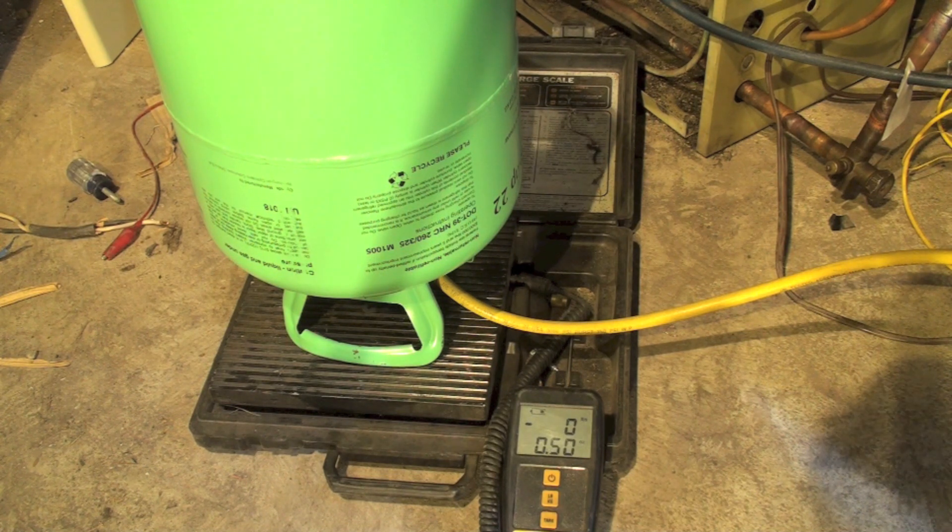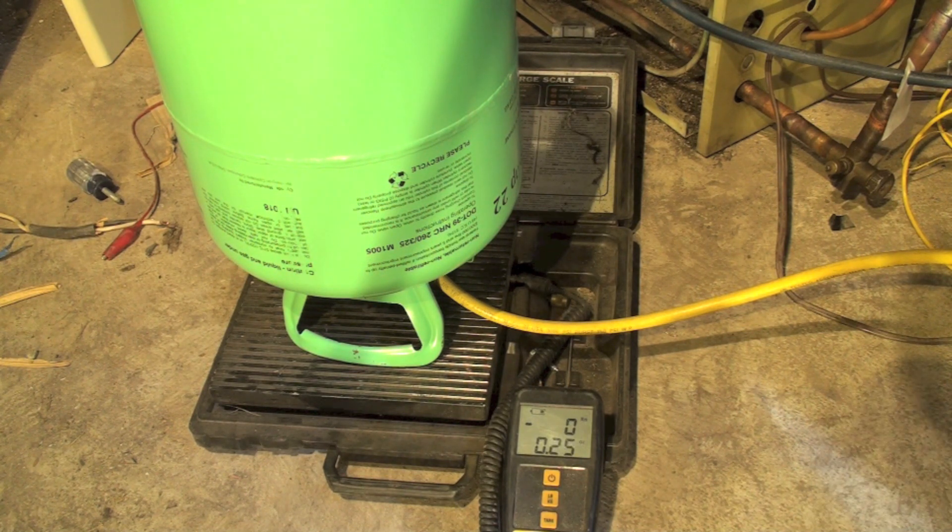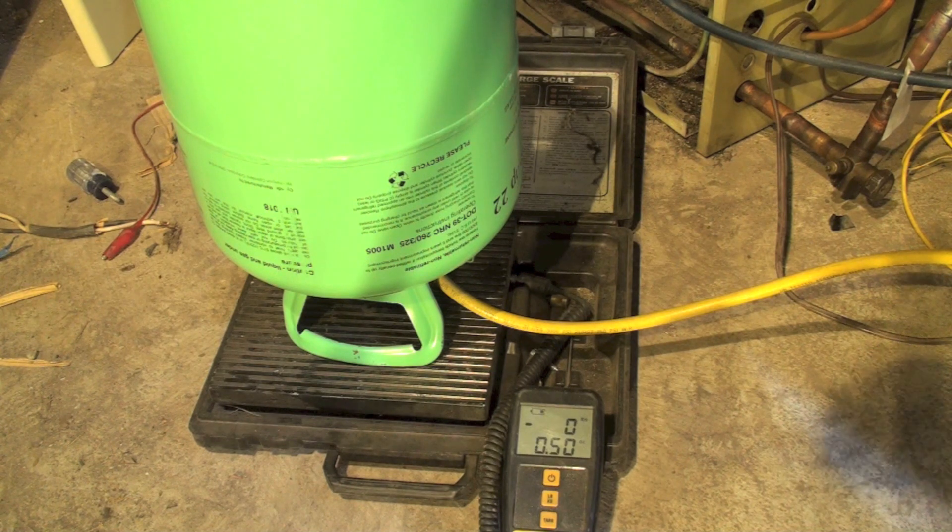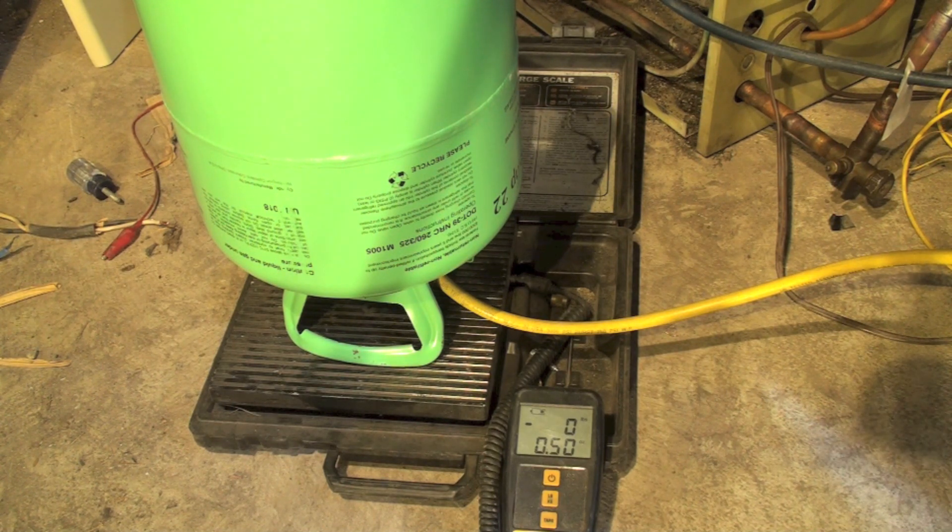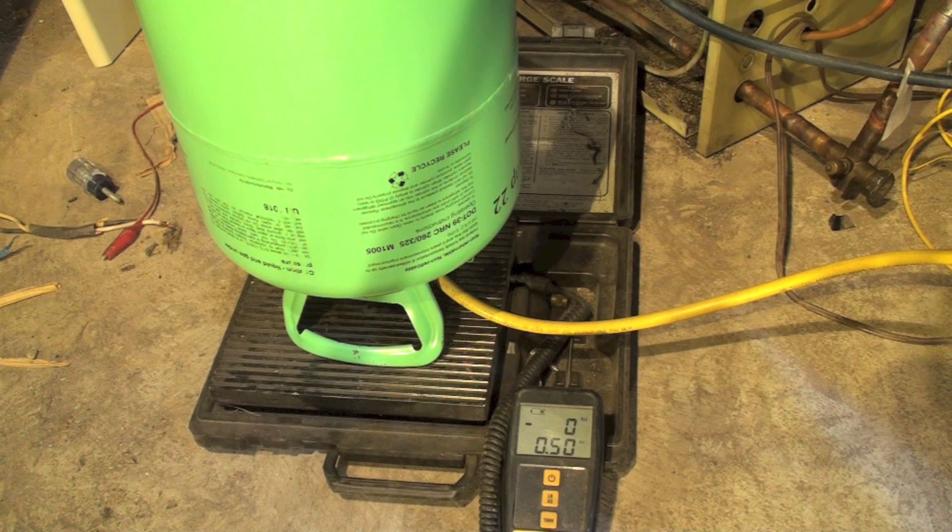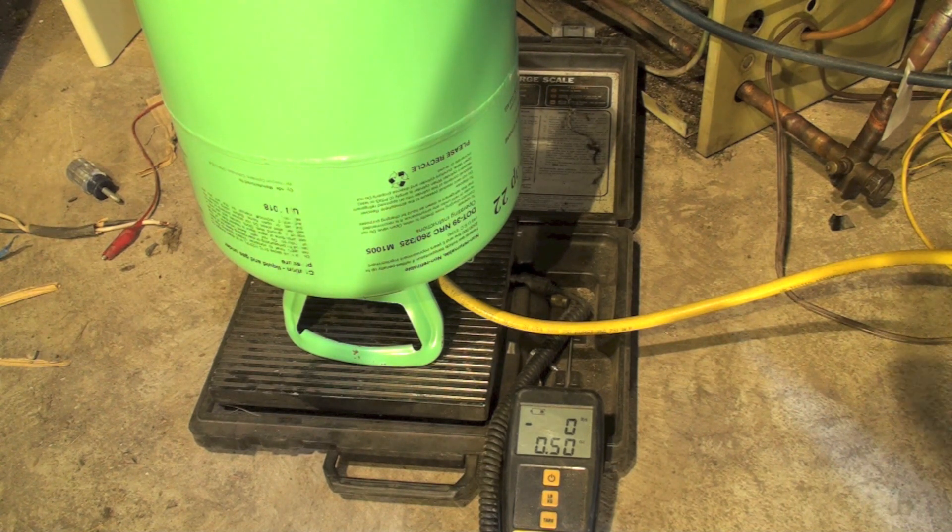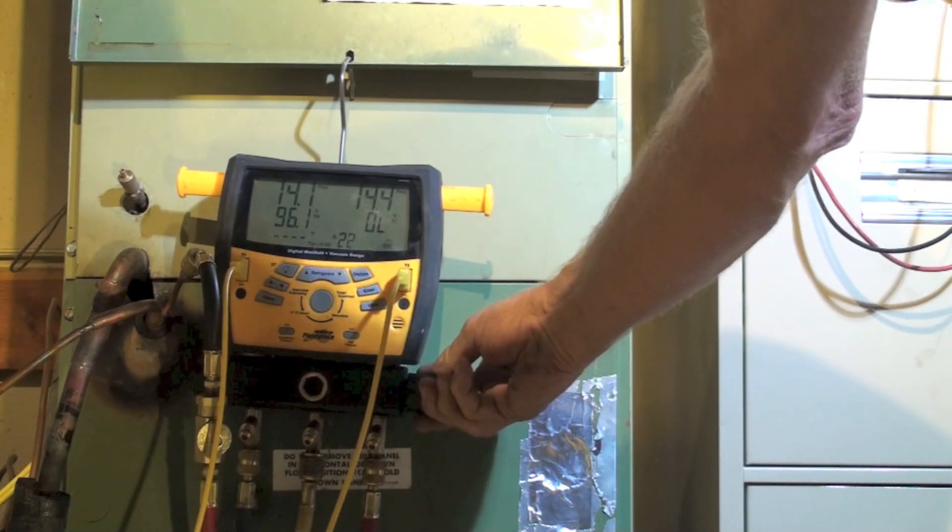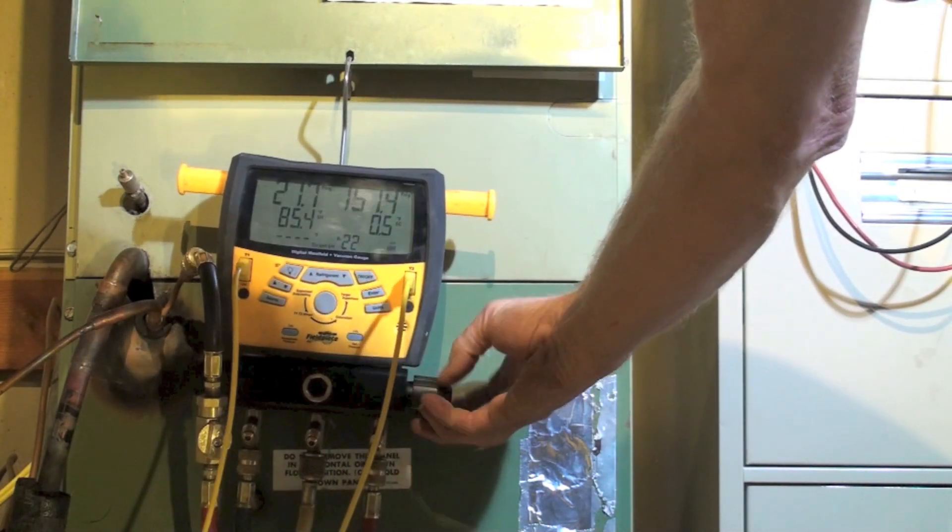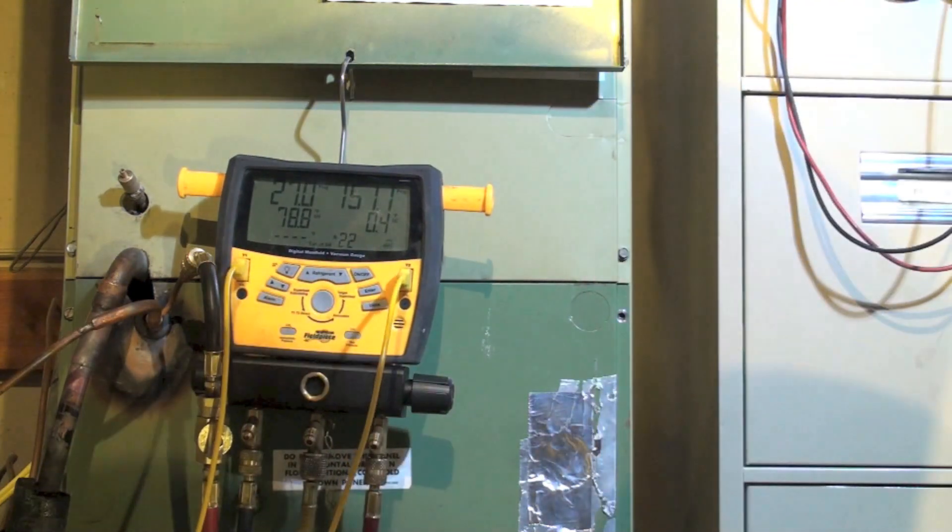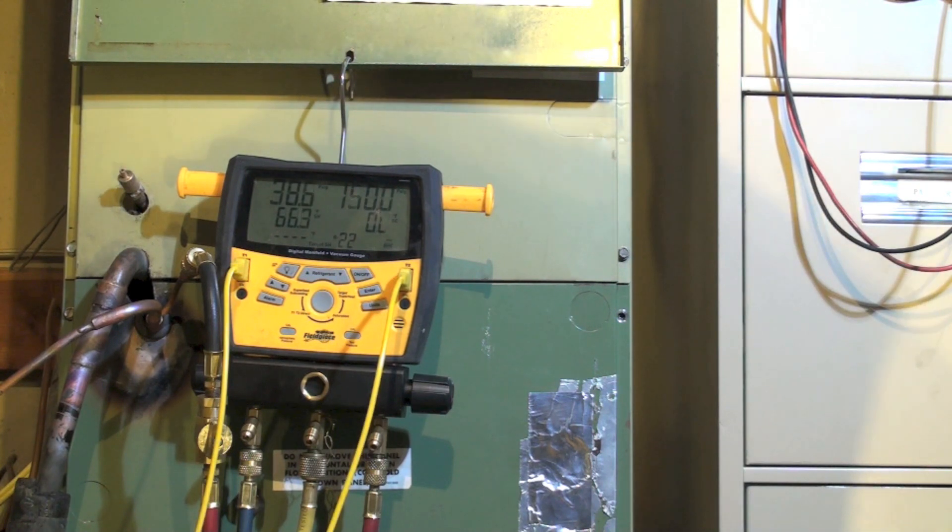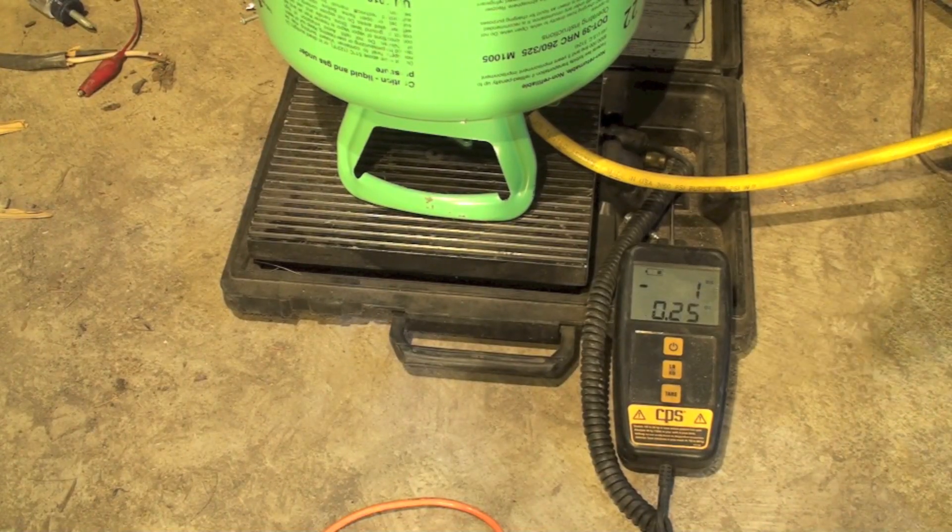Okay, again this is R22, so we have seven and a half pounds as a factory charge. We've got a 25-foot line set. That's probably going to be the right amount. We are going to check it with target superheat. Opening the high side valve, listen close you can hear it go in. I'm going to go back to the scale so you can see how we're doing. Okay, see we've got a little over a pound so far.